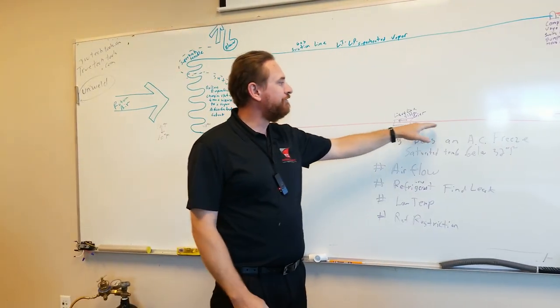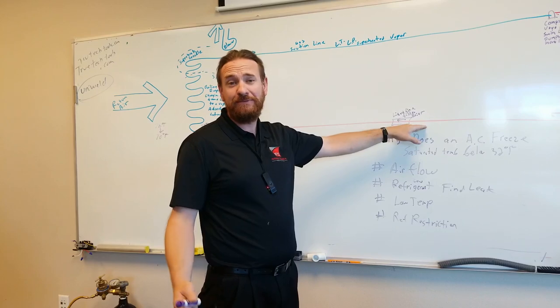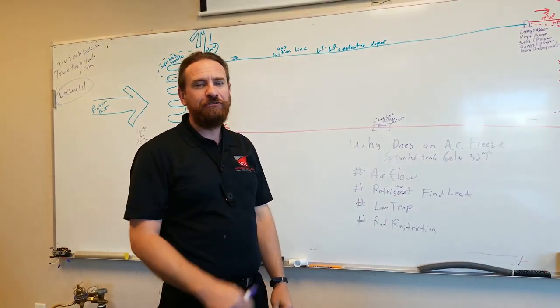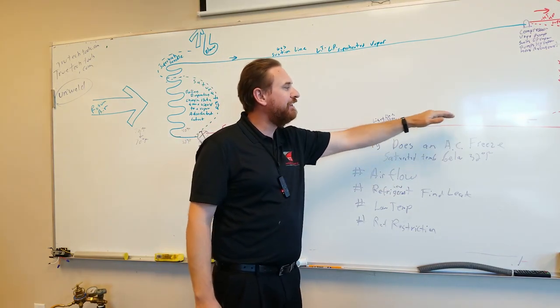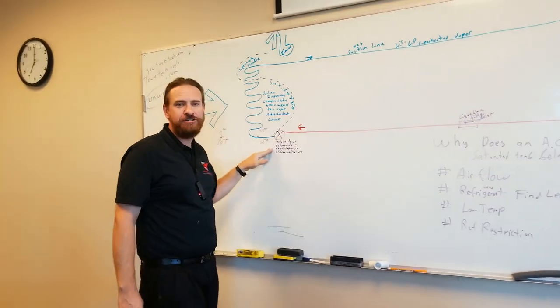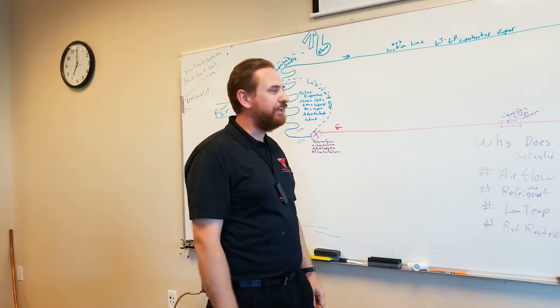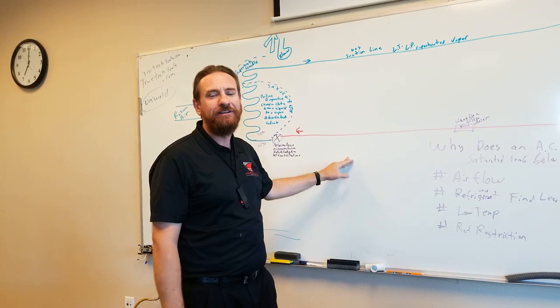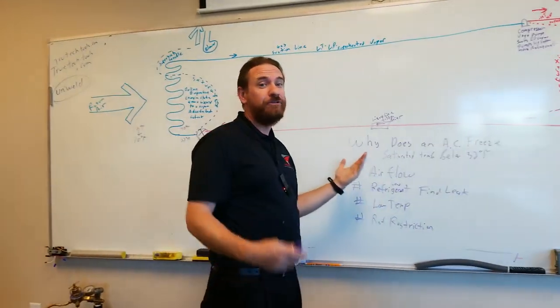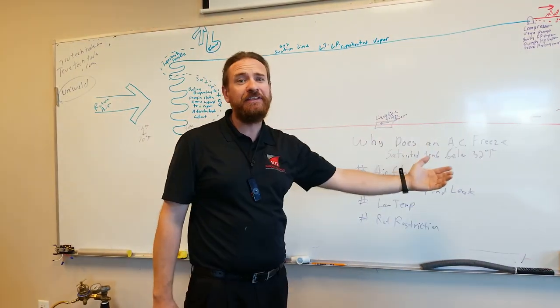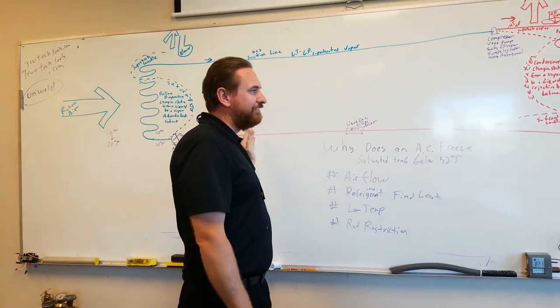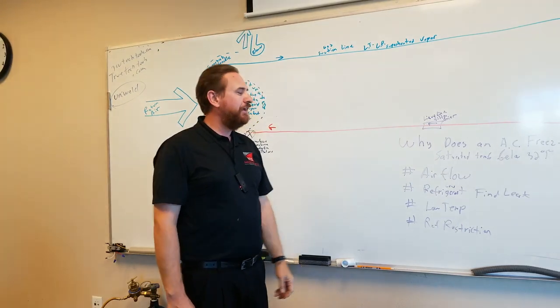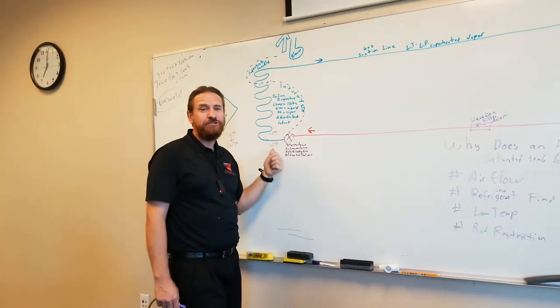Kinks in refrigerant lines are another restriction cause — when lines are run inside walls and kinked during bending, they restrict flow just like kinking a straw. The pressure drop across the kink drops saturation temperature. A quick check: temperature on one side where the line enters the wall should be close to the temperature on the other side — a significant temperature drop indicates a kink. Any component between the outdoor unit and the evaporator that could be clogged causing a pressure drop will cause the metering device to see too-low pressure and the unit will freeze.